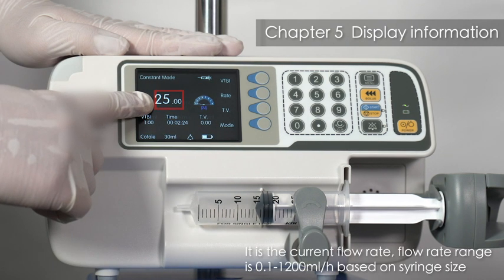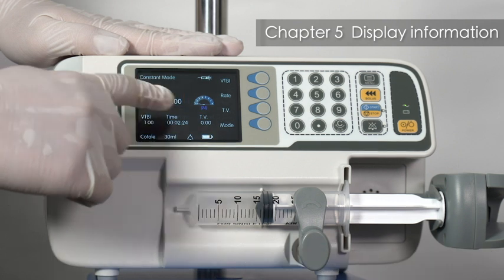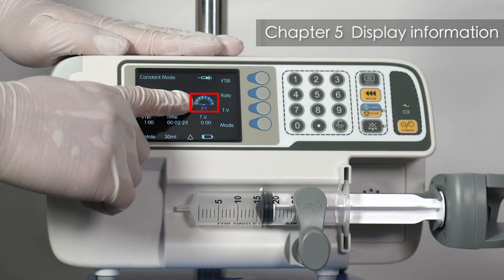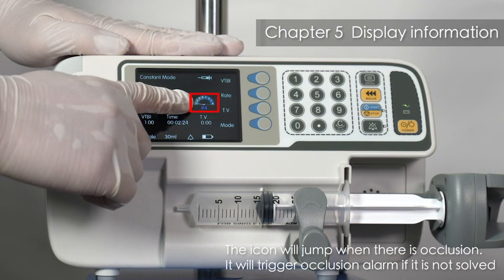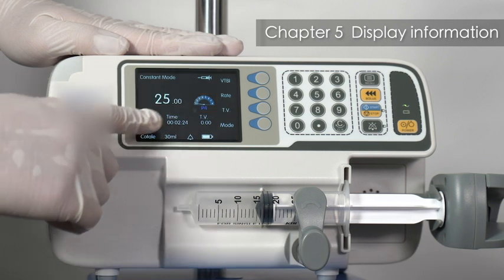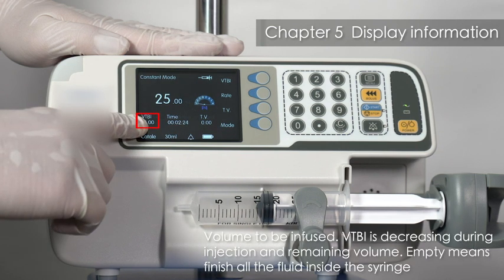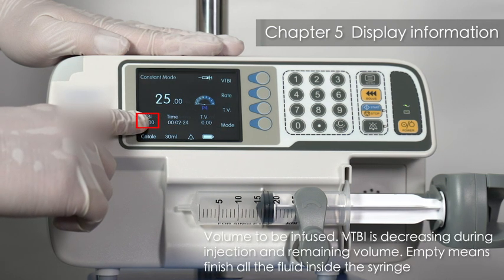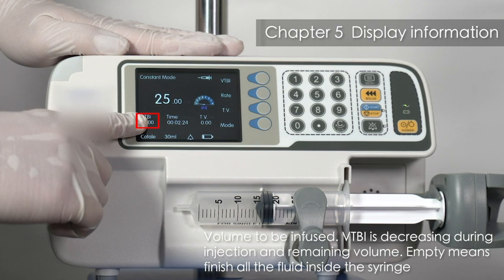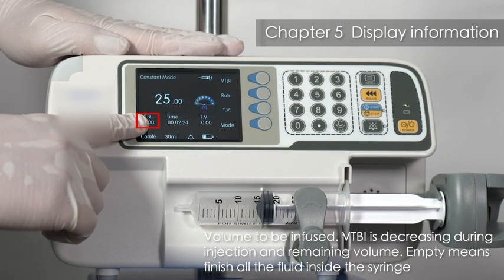Rate. It is the current flow rate. Flow rate range is 0.1 to 1,200 ml per hour based on syringe size. Pressure display icon. The icon will jump when there is occlusion. It will trigger occlusion alarm if it is not solved. VTBI, volume to be infused. VTBI is decreasing during injection and shows remaining volume. Empty means finish all the fluid inside the syringe.